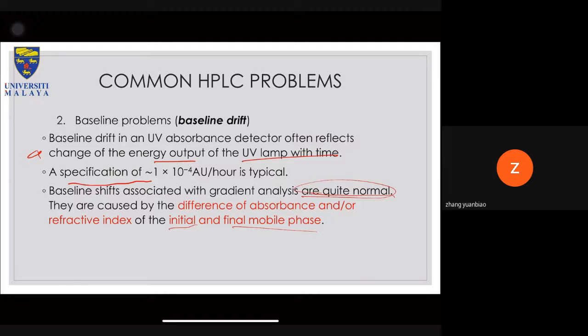So this is especially true if, say, for example, this is just based on the previous slide, if you are running 0% acetonitrile and you are finishing at 100% acetonitrile, you definitely know that at 0% acetonitrile, there is 100% of one type of solvent. Typically, for a reverse phase HPLC, it is water or ultra pure water. So similarly, at 100% acetonitrile, there's 0% of ultra pure water. So just looking at these two molecules, you do know that the absorptions are totally different, okay? Because they are different molecules. They have different vibrational bands. They absorb energy at a different wavelength, and so on and so forth. So there will definitely be a solvent baseline drift.